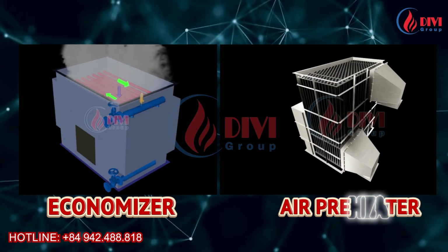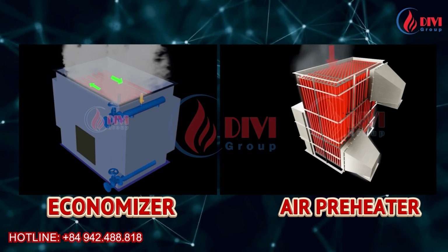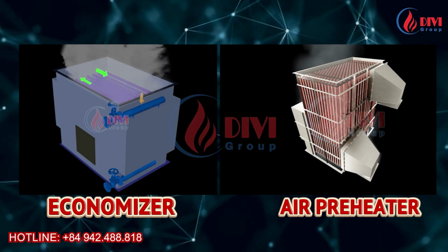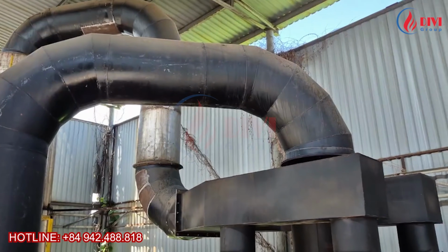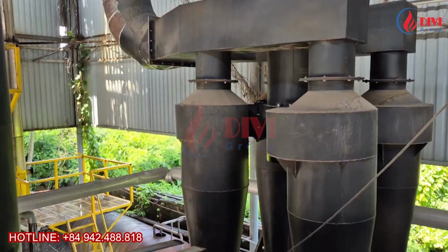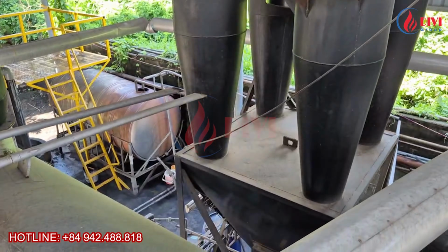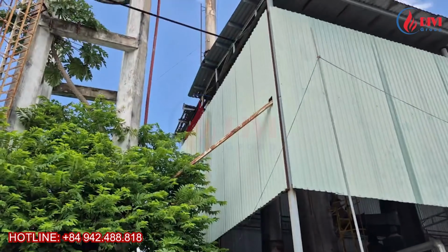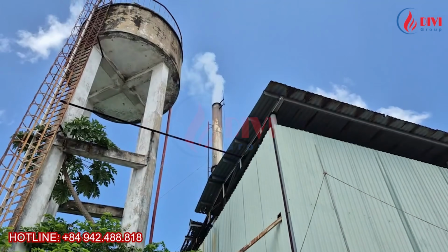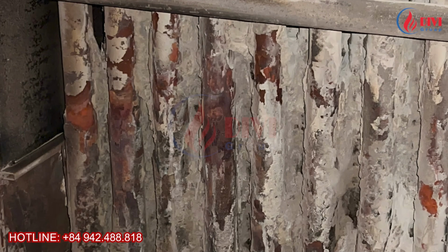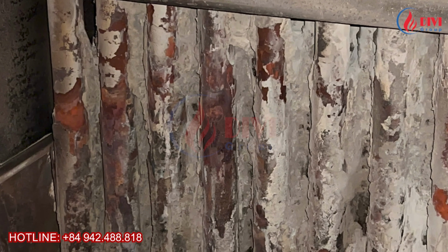Possible solutions include installing an economizer and installing an air preheater. These devices recover waste heat from the flue gas to preheat feed water or combustion air, thereby improving overall system efficiency. However, if your boiler already has a properly designed economizer and air preheater, but the flue gas temperature is still above 140 degrees Celsius, this is a strong sign that the boiler urgently needs cleaning. In many cases, excessive ash, dust, or scale buildup on the heat transfer surfaces is reducing heat transfer efficiency.